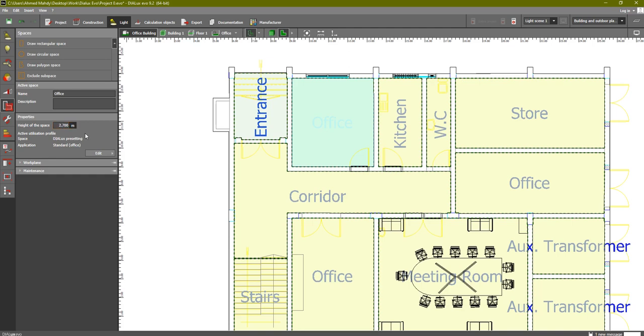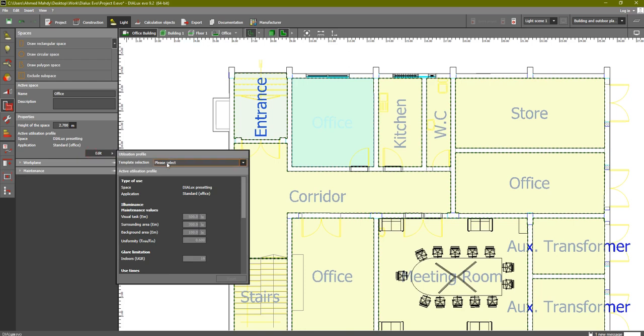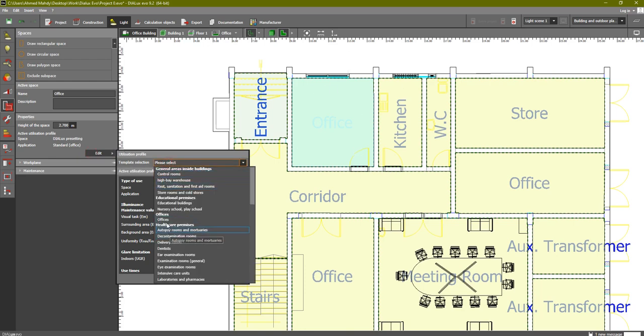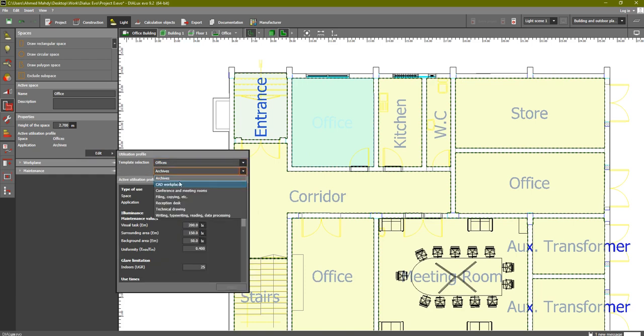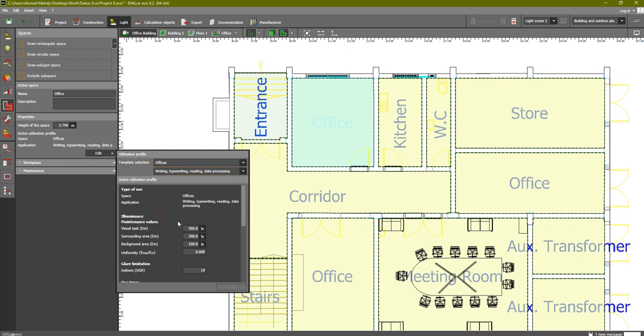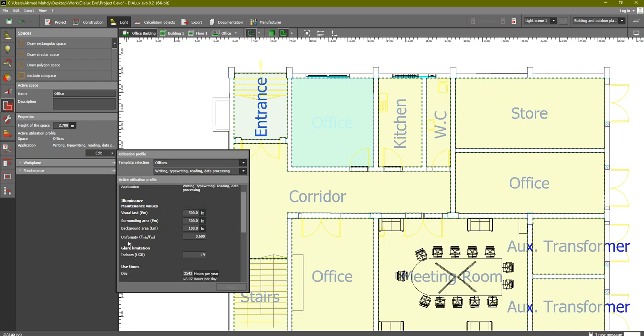Now click Edit and select the template for the office. Under Offices you can find archives, CAD, copying, reception desk, and so on. For a typical office — writing, typing, reading, data processing — you can see the code value is 500 lux and the uniformity, which is important in an office, is set to 0.6 by default.